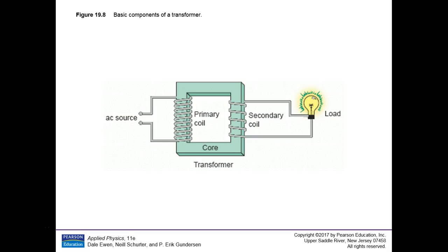At the generating plant, the power station, wherever you got your power, that's producing a certain amount of electricity: voltage, current, power. Okay? And what happens there is they step it up like crazy, so it's very high voltage. The reason for that is most of your line loss comes from the current, because the more the current, the more heat produced, more friction is going on. So if you can minimize the current, you can minimize line loss. Minimizing current means maximizing voltage.